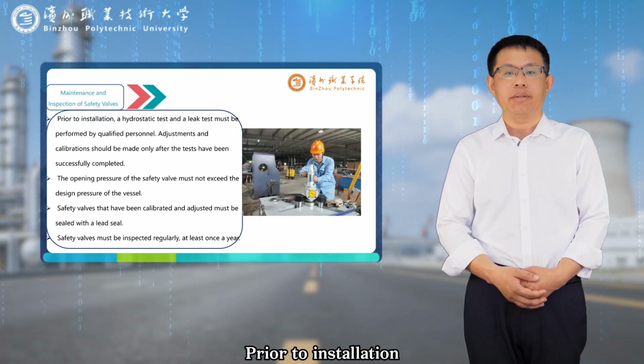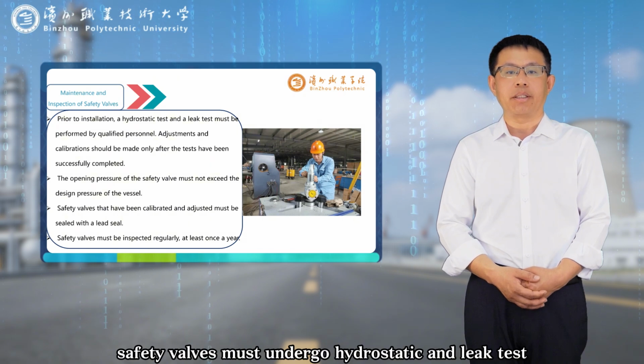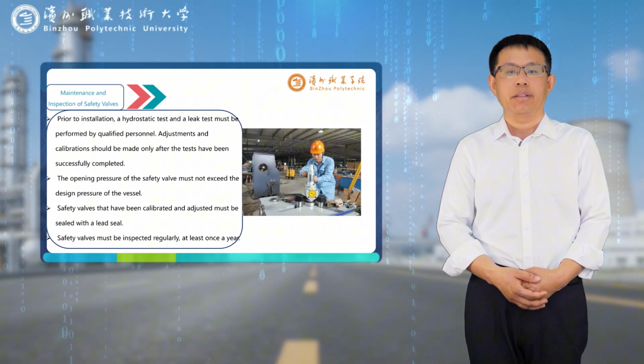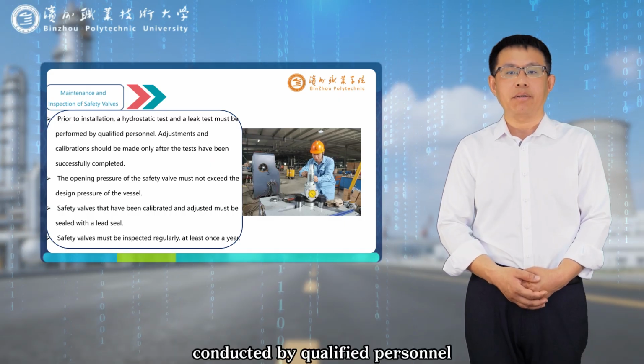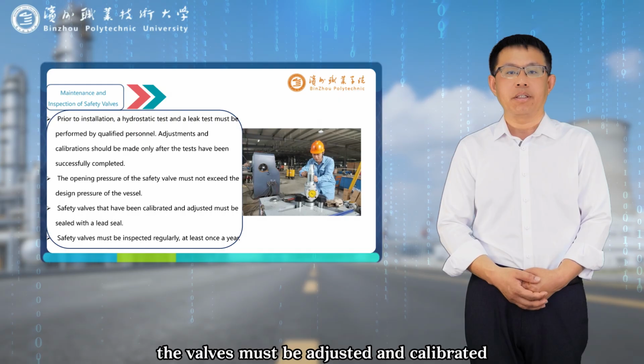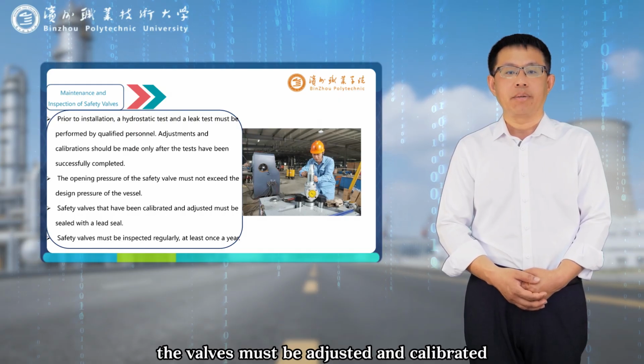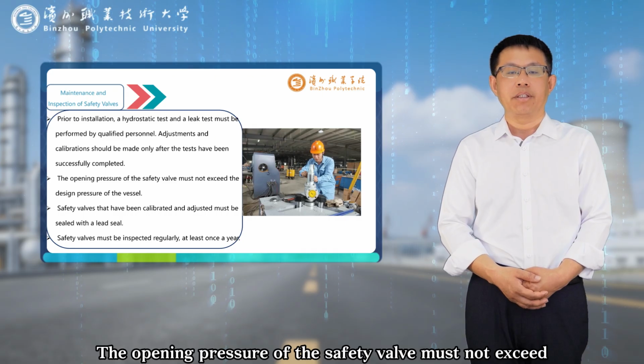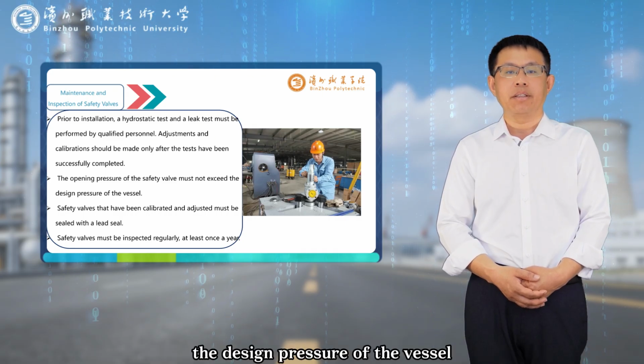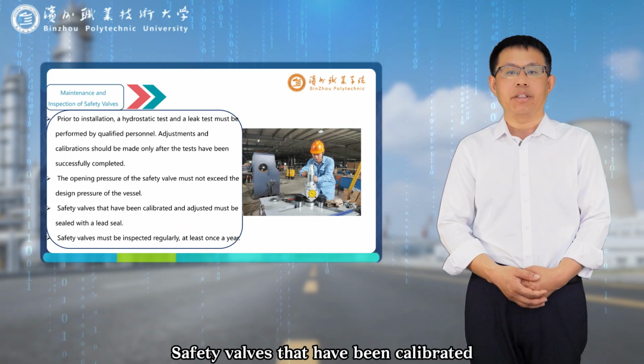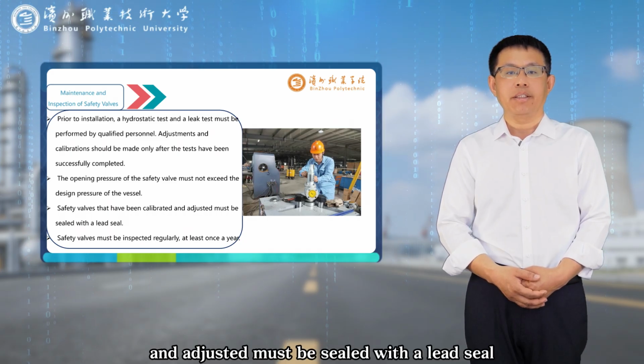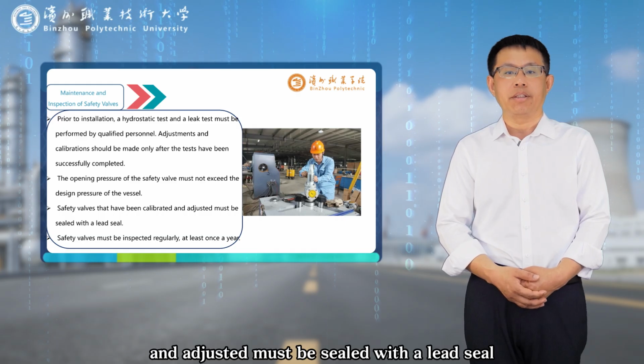Prior to installation, safety valves must undergo hydrostatic and leak tests, conducted by qualified personnel. After passing these tests, the valves must be adjusted and calibrated. The opening pressure of the safety valve must not exceed the design pressure of the vessel. Safety valves that have been calibrated and adjusted must be sealed with a lead seal.